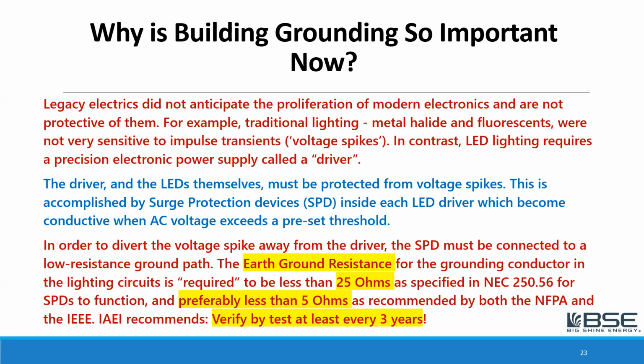So why is building grounding so important now? Well, the fundamental reason is that in the past, legacy electrical systems didn't really anticipate the proliferation of modern electronics, and they're not protective of them. So for example, just to cite the example of lighting, all of the commercial lighting out there before, metal halide, fluorescent, they were not very sensitive to impulse transients, the kind of spikes I showed you in that waveform. But in contrast, every LED fixture now has a precision electronic power supply called a driver. That driver has to take AC power at a high voltage level and convert it to a very low voltage DC, which is carefully regulated. And that's not easy. The electronics in there are vulnerable if there are a lot of disturbances on the power supply, on the power equipment.